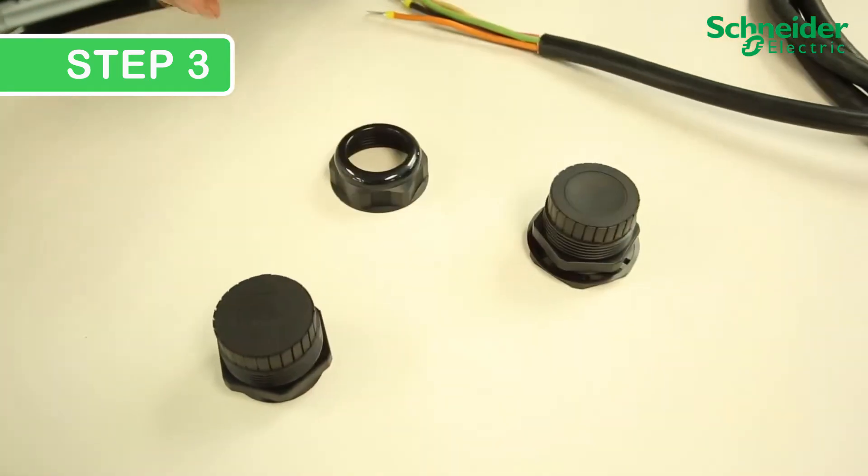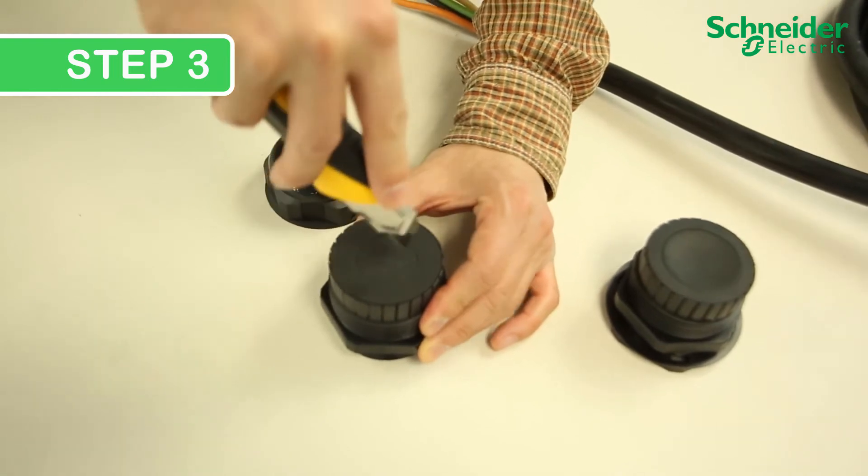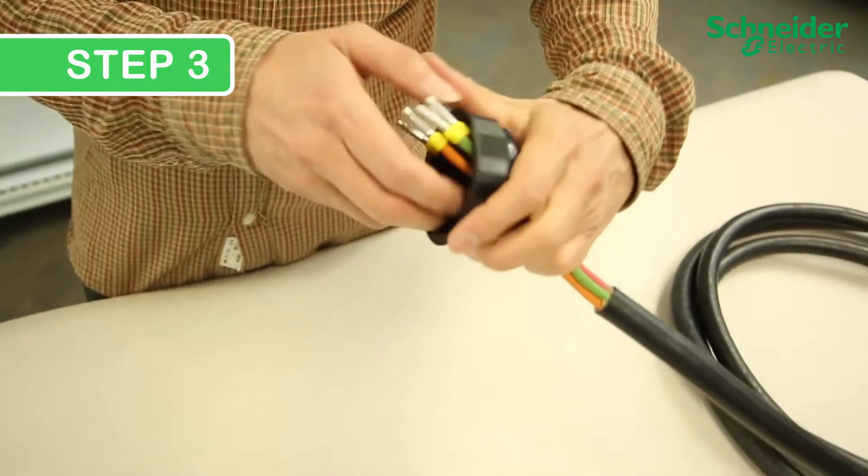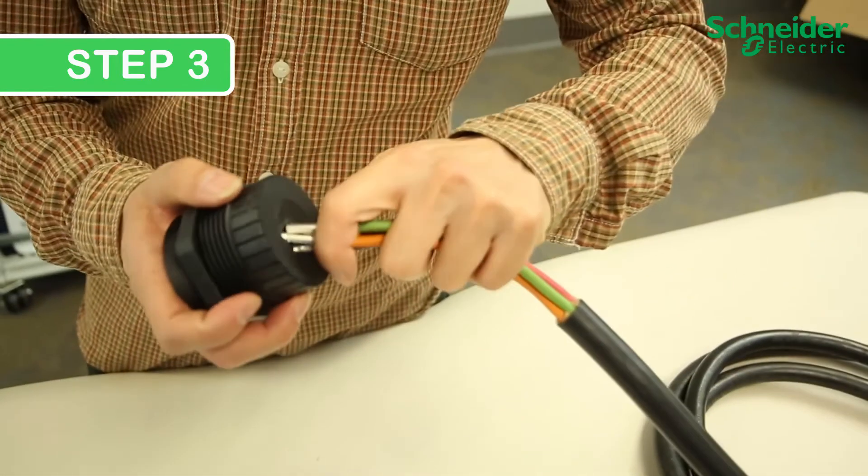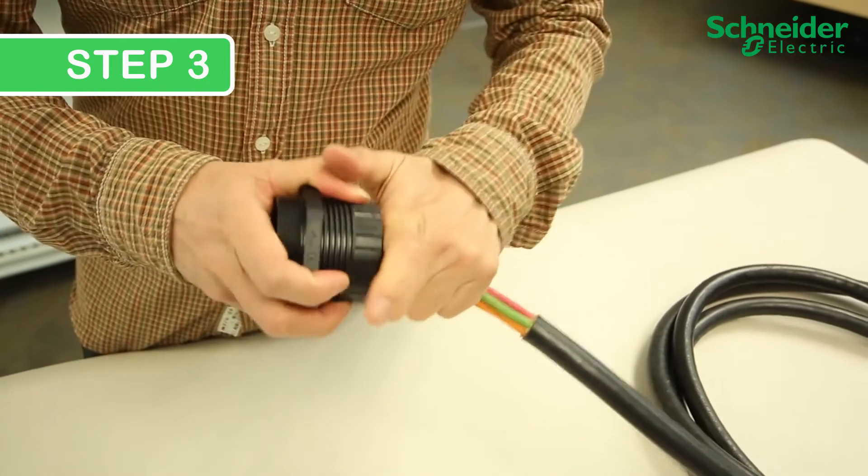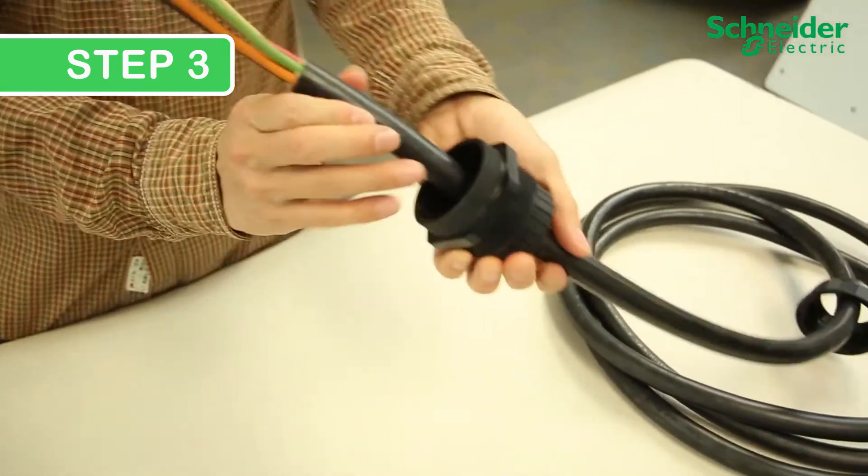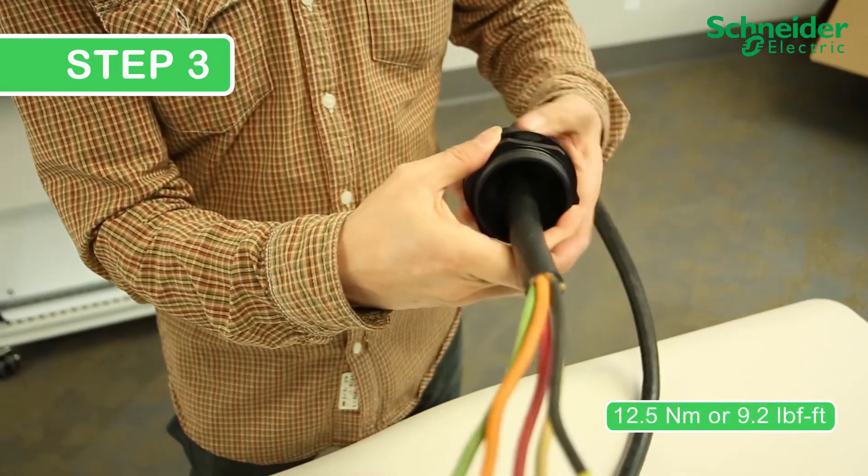To install the cable through a gland, make a small incision. Insert the ring and push the cable through incision in the AC gland. Tighten the ring over the gland to 12.5 Nm or 9.2 lb.